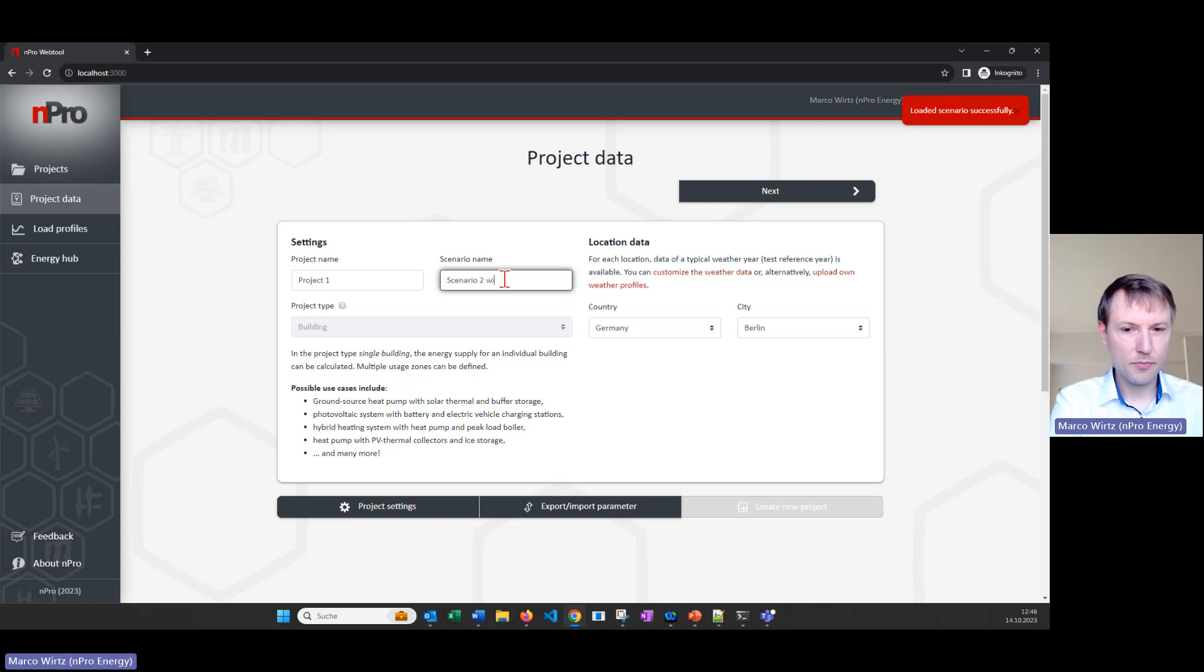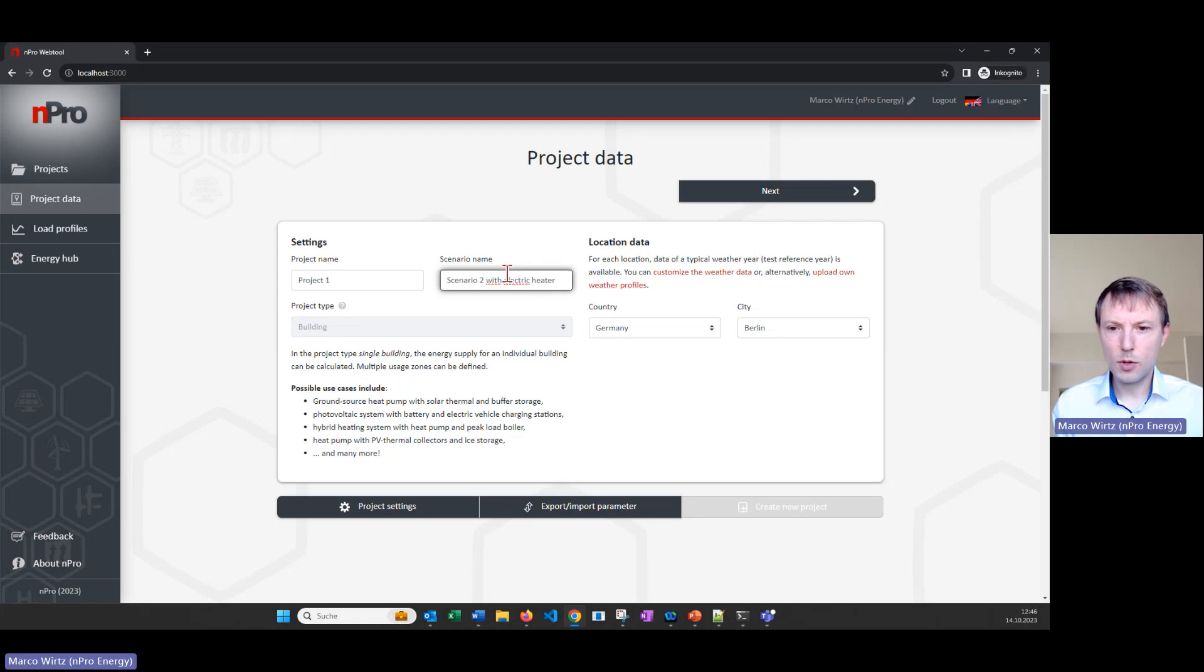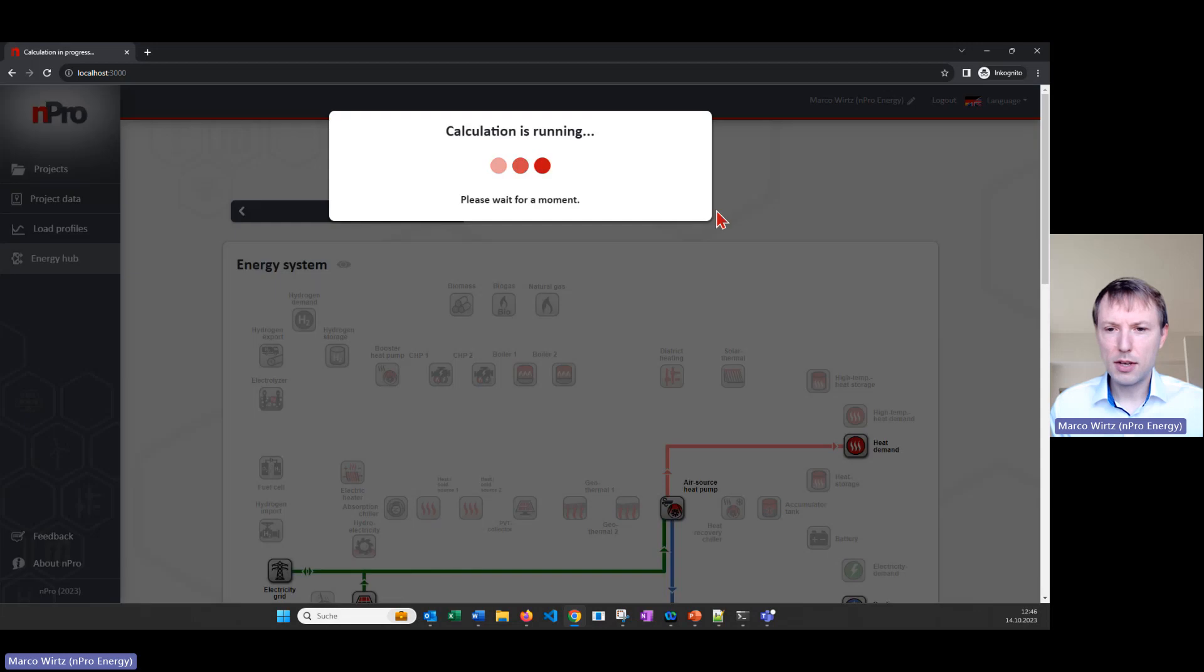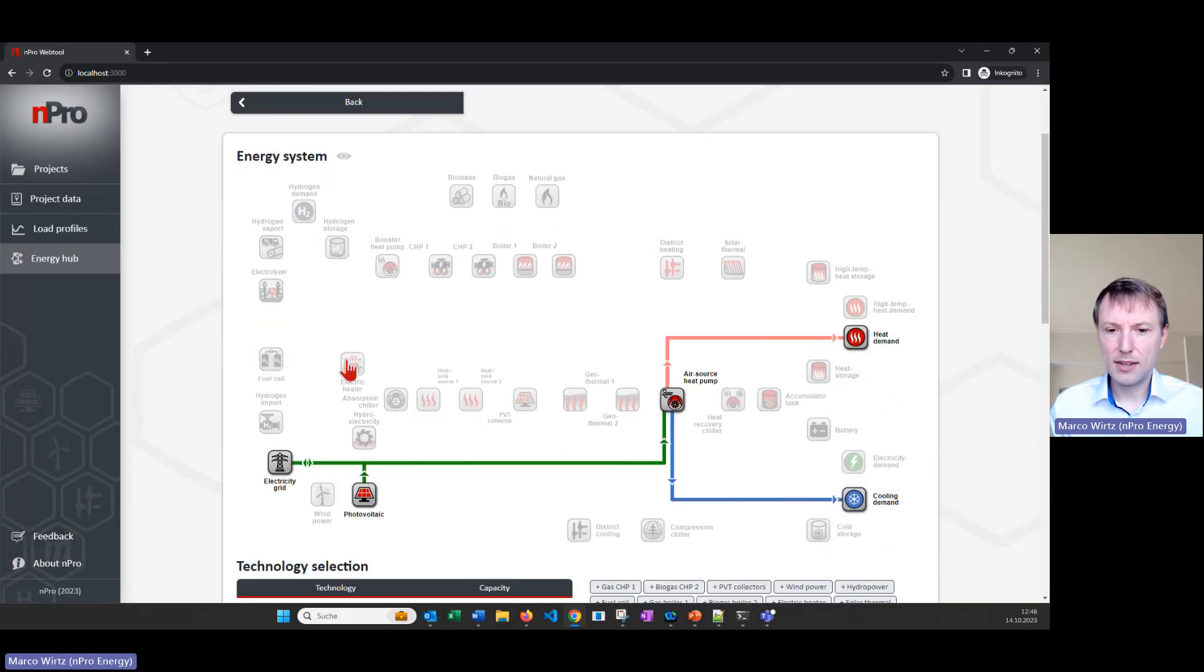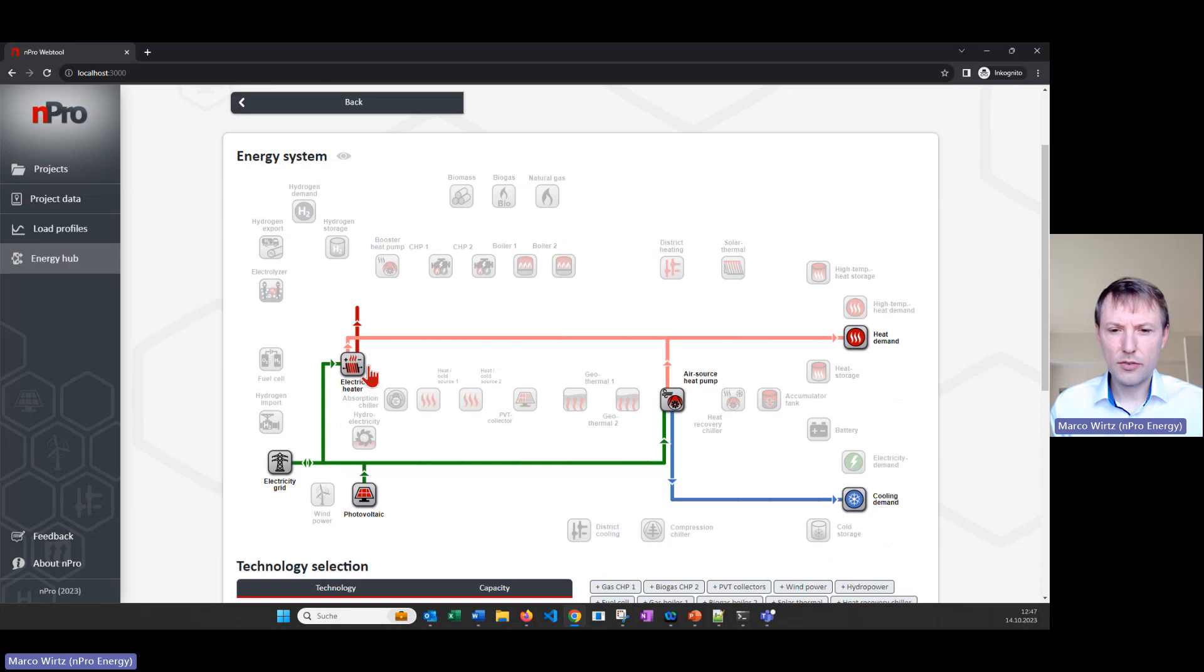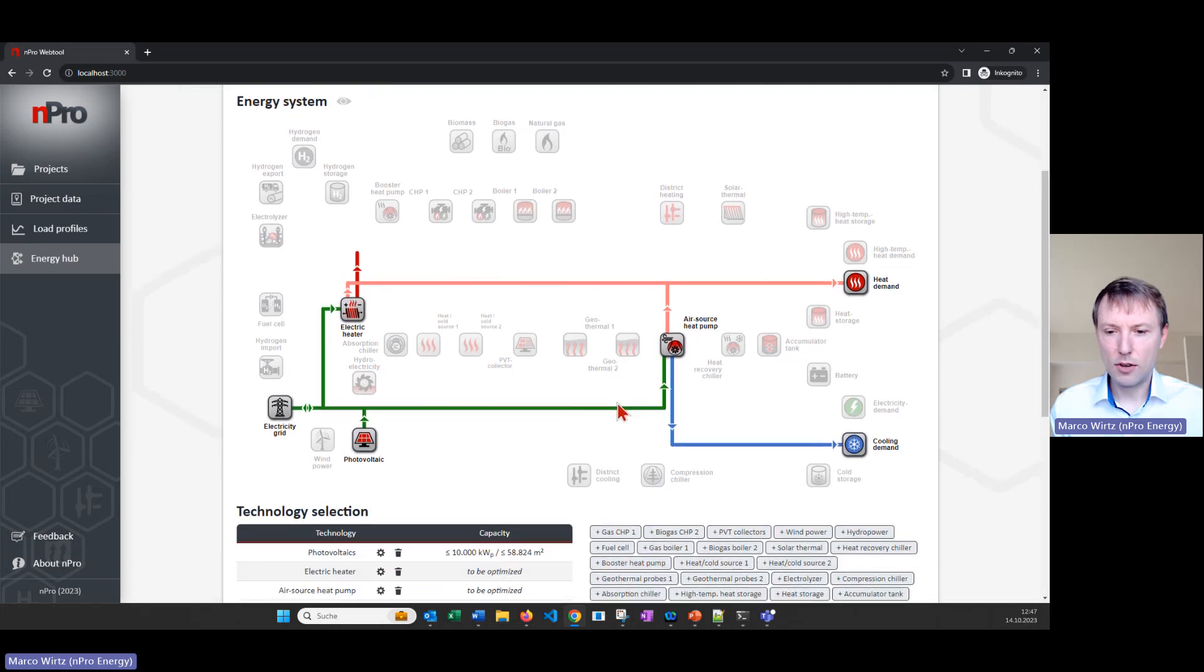And then we have here now two scenarios. The first one is a PV air source heat pump scenario and the second one is a duplicate of that and I will change it and say now with electric heater. So we will simulate the same again but now we will not only have the air source heat pump but I will also add an electric heater for example for covering the peak loads. Then we can dimension the air source heat pump a little bit smaller.